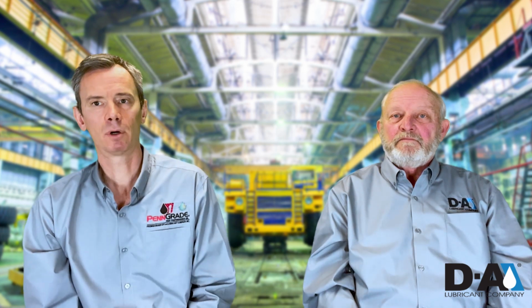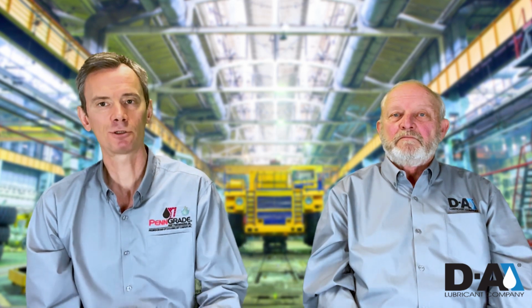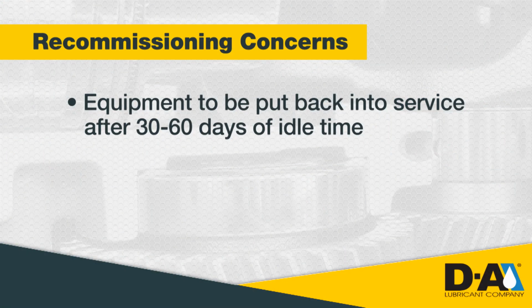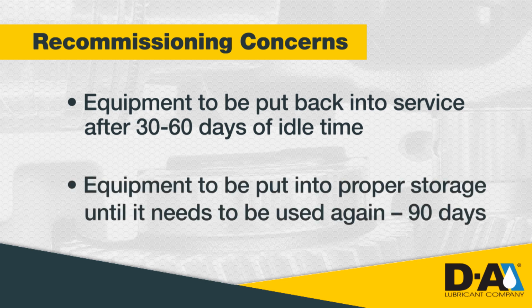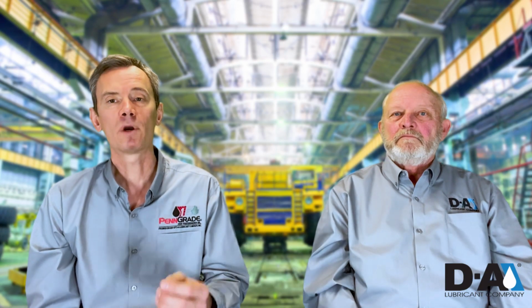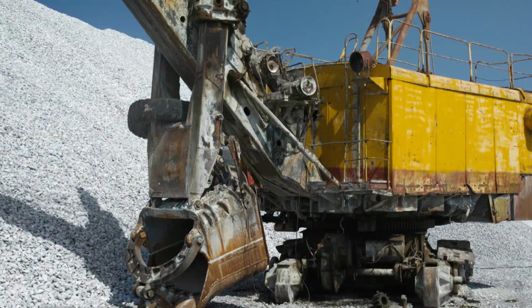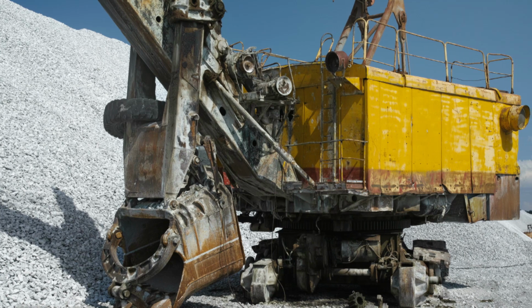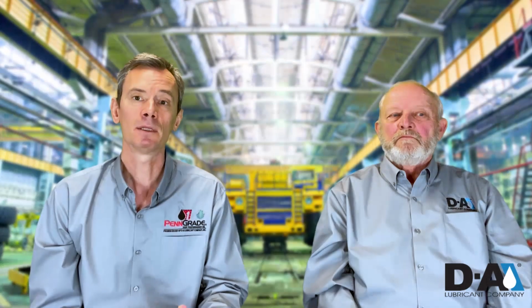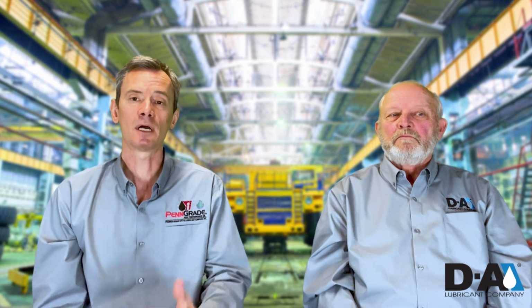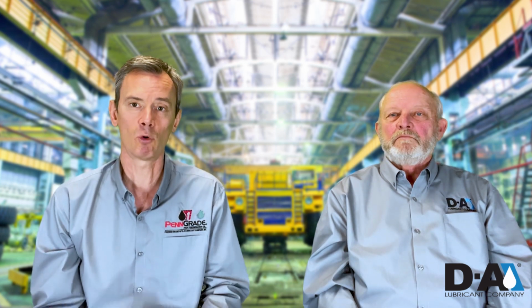Now, as we come back to work, there will be two commissioning concerns. Number one, equipment to be put back into service after 30 to 60 days of idle or static period storage. And two, equipment to be put back into proper storage until it needs to be used again, 90 days or so. Remember, every machine is different. Take the time to go over recommissioning procedures set forth by the OEM, the original equipment manufacturer. Let's start with 30 to 60 days sitting idle or static.